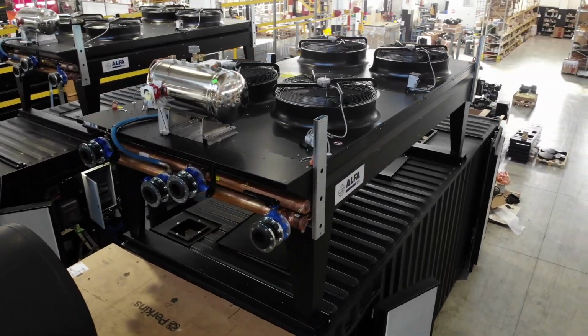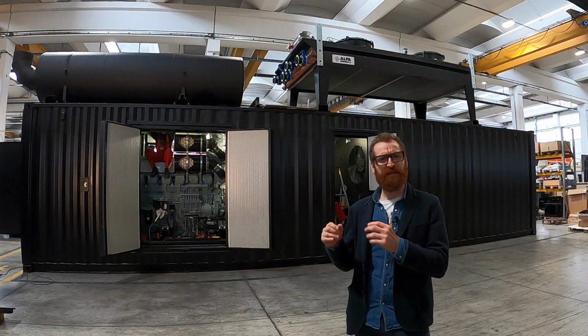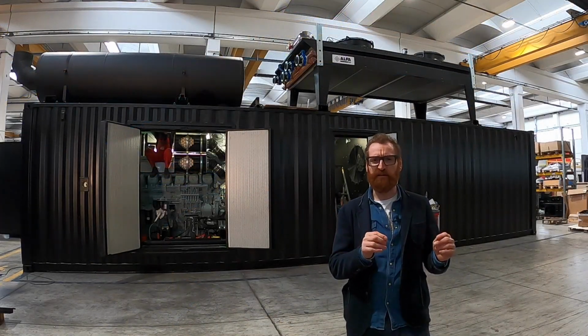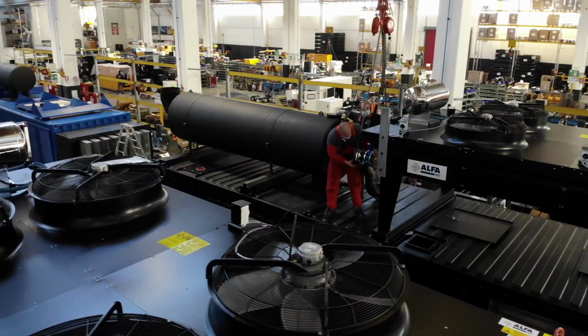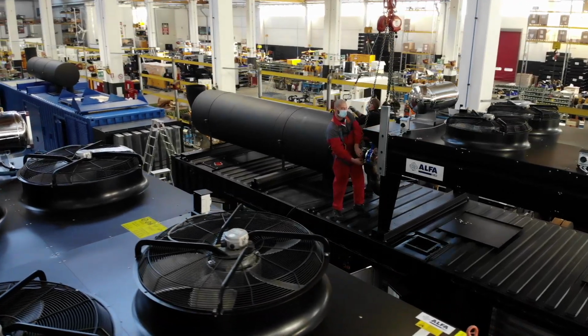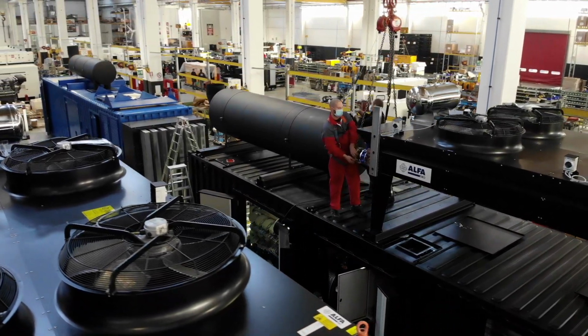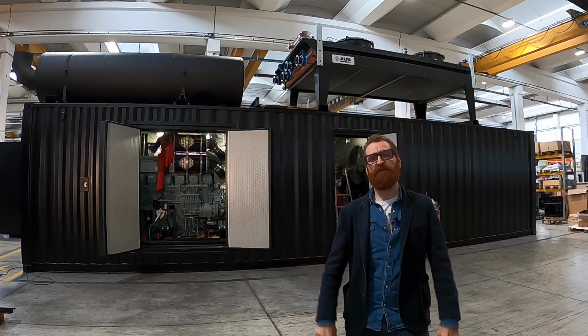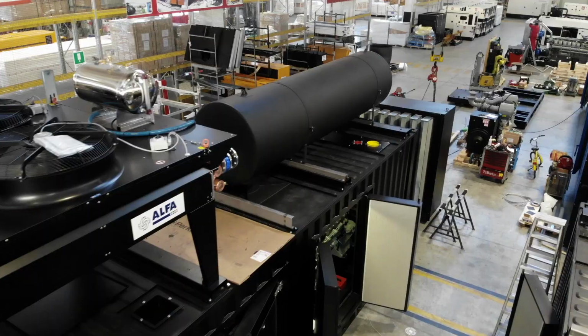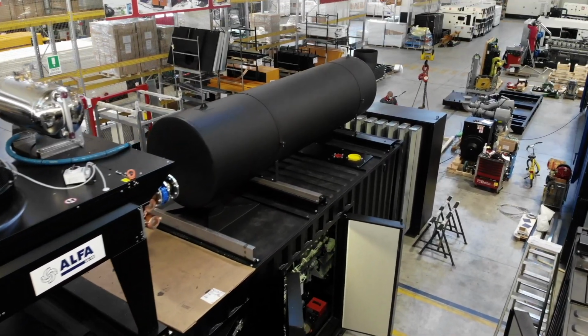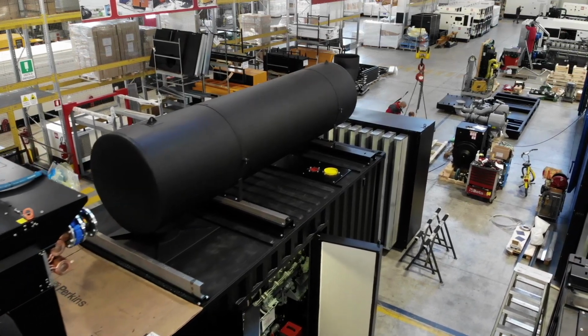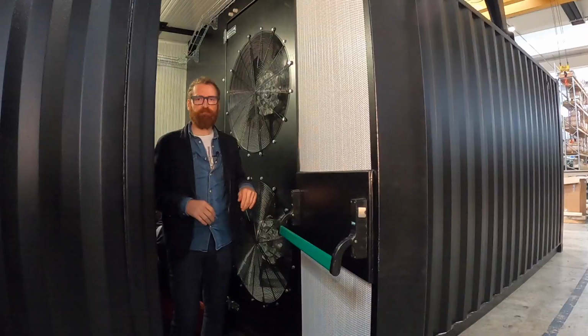The remote radiator permits us to install dedicated noise reduction baffles in the inlet and outlet channels. And furthermore, we have installed on the top of the roof a really big residential muffler, more than 5 meters long and with a diameter of 1.1 meters.